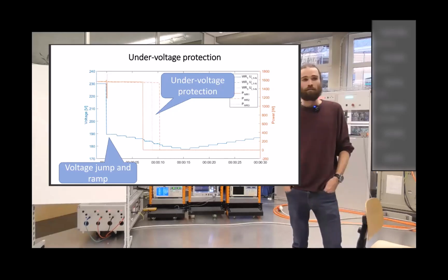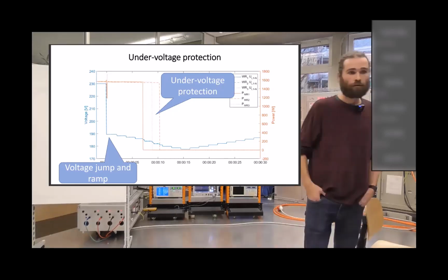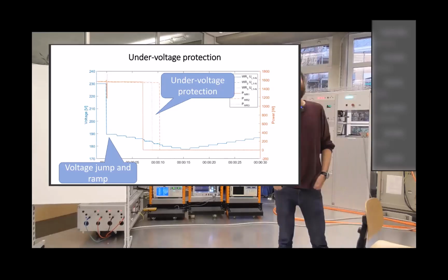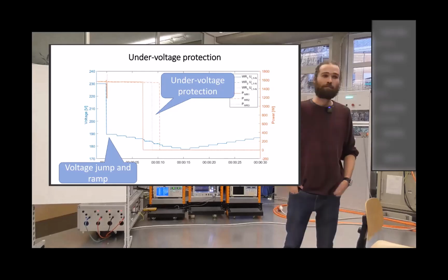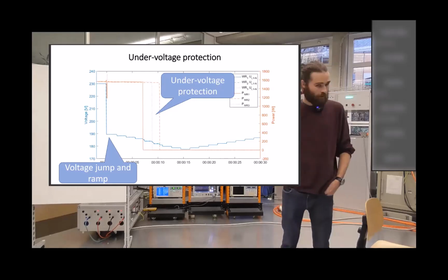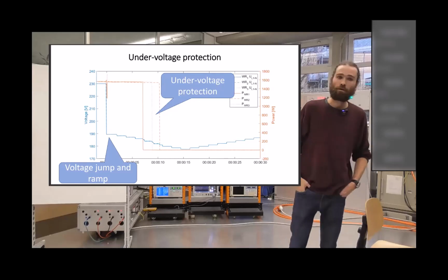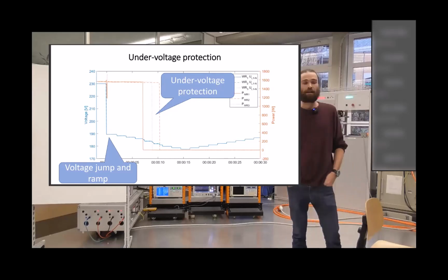And the step you can see in the three orange lines, this is when the three inverters disconnected and the power they inject to the grid went to zero. As you can see, they weren't really at the same time. They had just a space between, but all of them were in the standards. They passed the test and were in the tolerance.